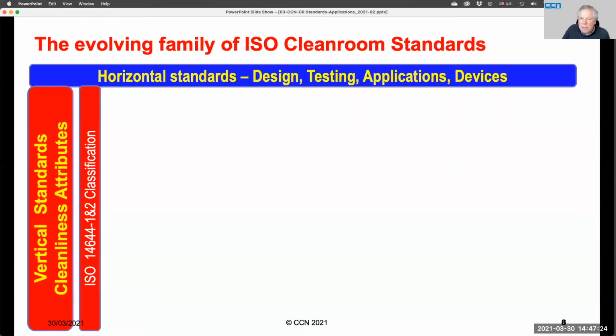Just while I'm talking about the standards, be aware that these standards are evolving continuously, and sometimes we need to refer to the standard with a date annotation, usually after a colon, and sometimes we refer to it without a date, or regulatory instruments sometimes refer to the standards without a date. If the standard is referred to without a date, this means always it is the latest version. If it's referred to with a date, then it is the specific published version with that date. So that's an important point of semantic detail. Very often I see in documents "comply with ISO 14644." Completely meaningless. So be a little bit fussy and picky, please, on your nomenclature when referring to the standards.